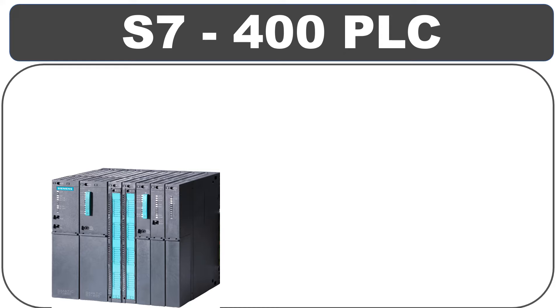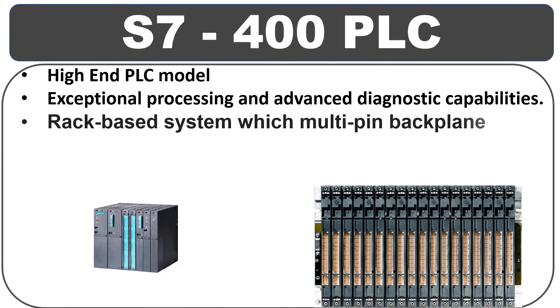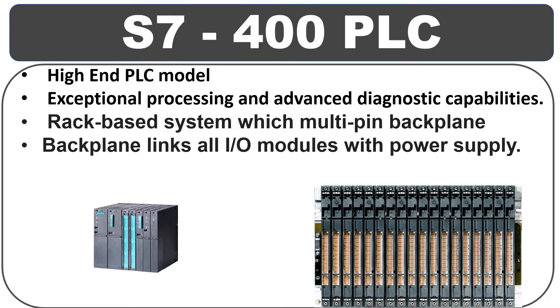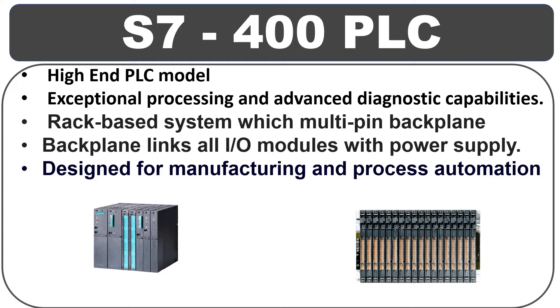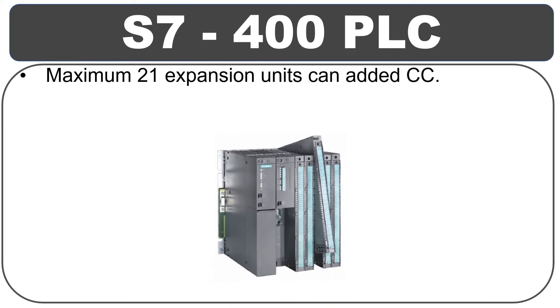The fourth PLC from Siemens is the S7-400 PLC. The S7-400 is a high-end PLC model that offers exceptional processing power and advanced diagnostic capabilities. It is a rack-based system in which a multi-pin backplane links all the I/O modules with the power supply. The S7-400 has been designed for the field of manufacturing and process automation and can handle massive process data. A maximum of 21 expansion units can be connected to the central controller.